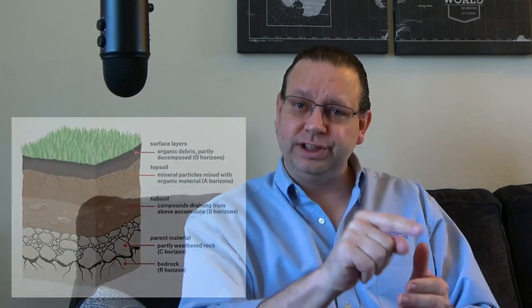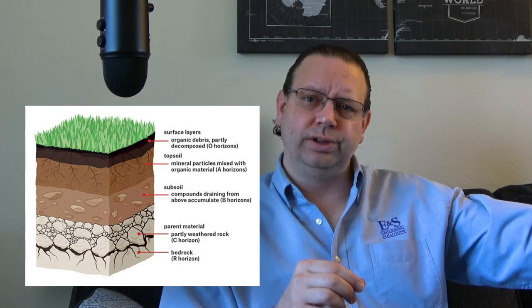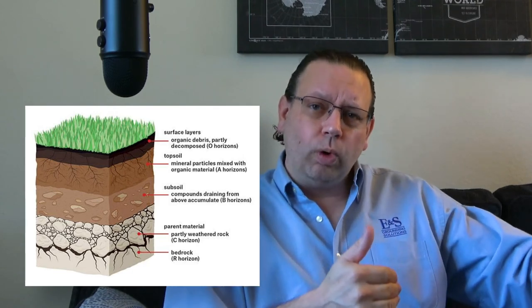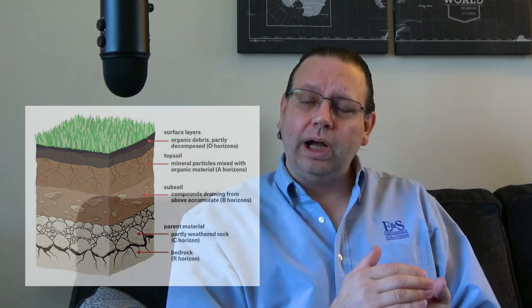And just to wrap up, you can consider it resistances in parallel. Think of the earth as cubes that are one meter by one meter by one meter, and if we assign a resistor to each one, we get resistances in parallel. The more copper we can put across those resistors, the lower and lower the resistance to that electrode is going to be, because we're getting across more and more parallel resistances. This is the power of the sphere of influence, and it ultimately drives the resistance to ground of your electrode system. This is the sphere of influence—it's a theory that tells us the amount of soil a given electrode system will utilize to dissipate electrical energy into. Thank you.